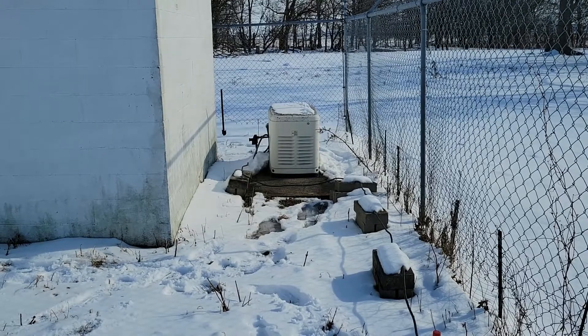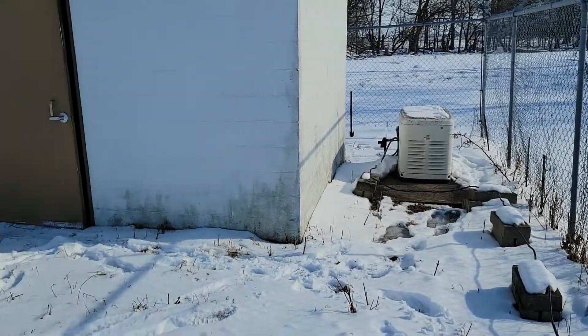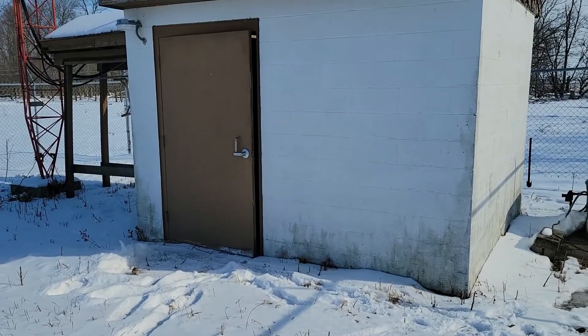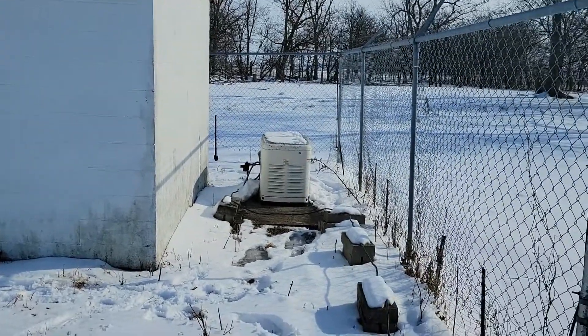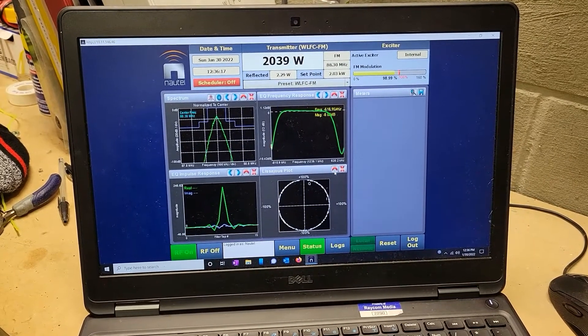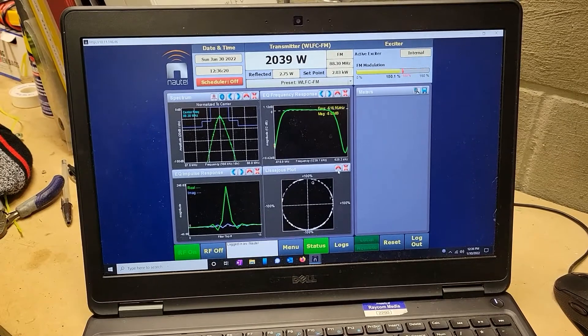One of the things I often get asked is what do you do at the transmitter site. Well, every month I run this generator and every month I transfer the entire building's electrical load onto the generator to make sure that it can handle it and run properly.